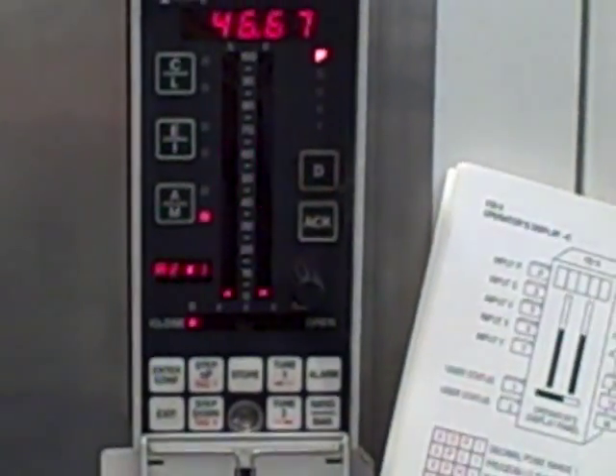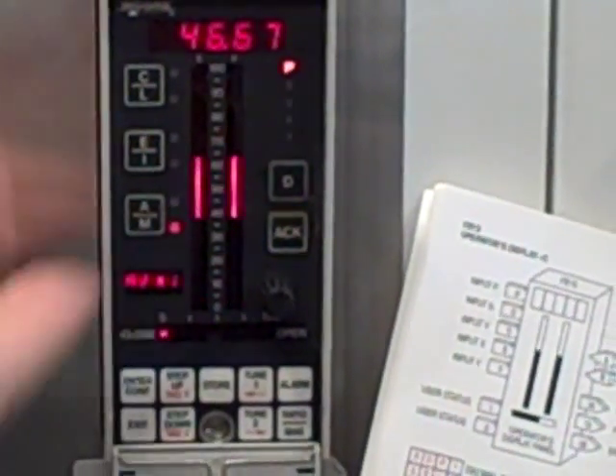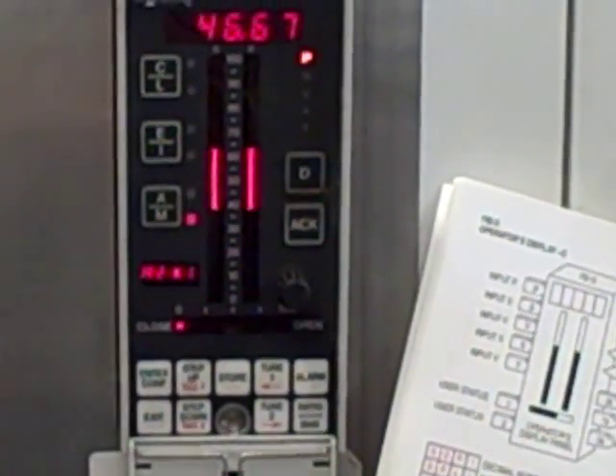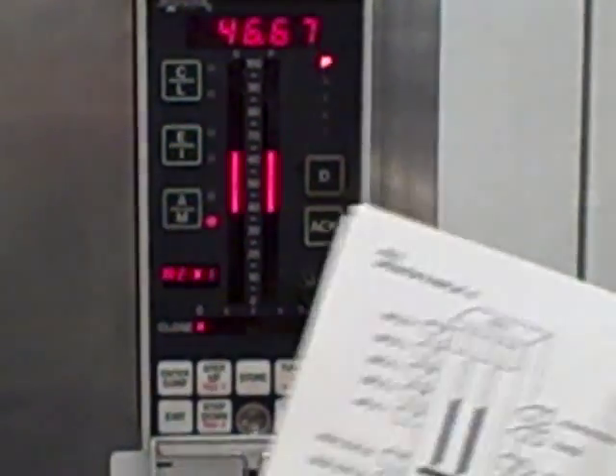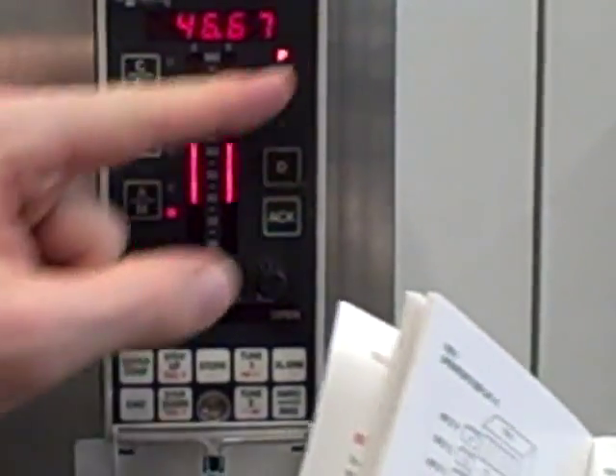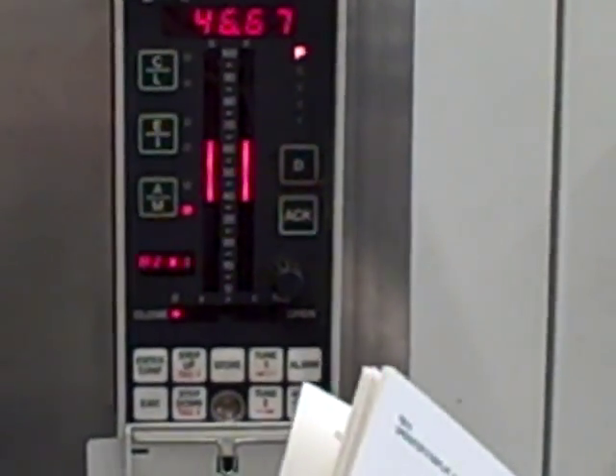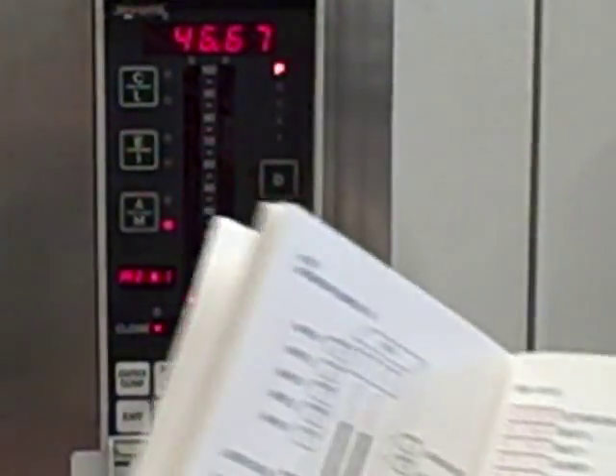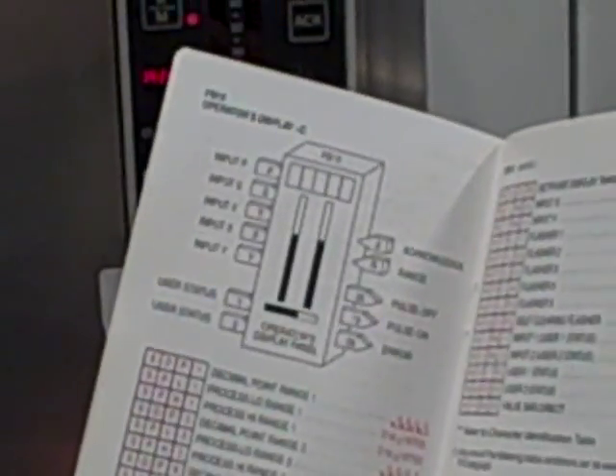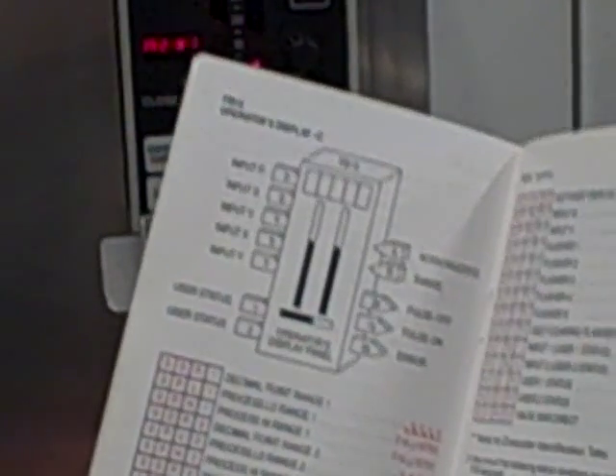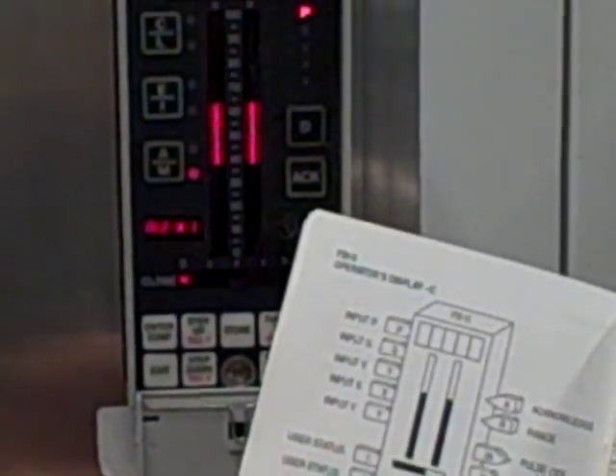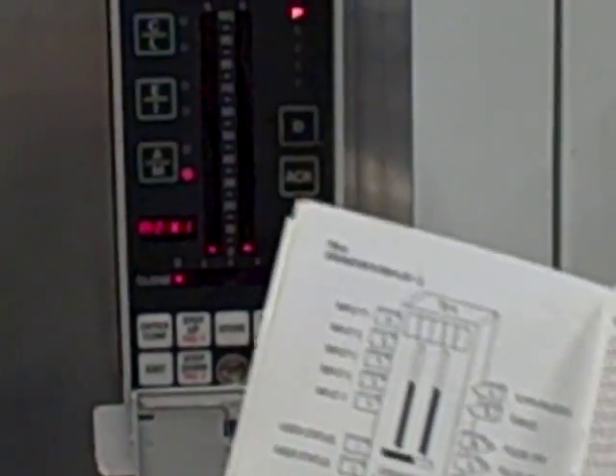It's actually 46.67 because it's under ranged. It will top out at 150. The bar graph still goes 0 to 100%, but my numerical values will range 50 to 150, and that will match your transmitter. So when the next person in the lab team changes the range on their transmitter, they'll have to come over here and change it accordingly in function block number 15 to match.